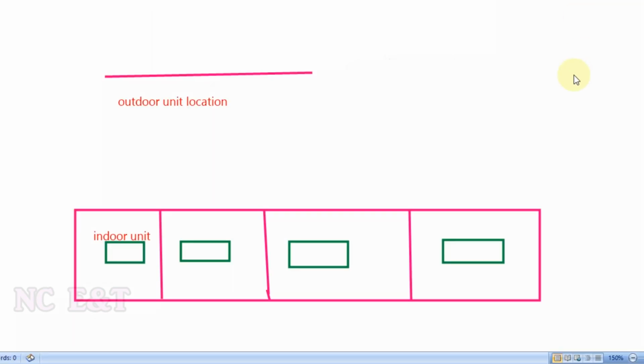Designing the VRF system, the first stage is to calculate the load of the room. We already studied heat load calculation in one video, so we will suppose that we have already calculated the load for the rooms. On the basis of the calculated load and as per the requirement of the room, we will select the indoor unit capacity. So now we have selected the units as per the heat load calculation: for room number 1, 5 ton, for room number 2, 7 ton, for room number 3, 10 ton, and for room number 4, 9 ton.